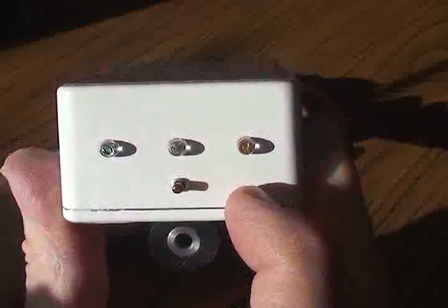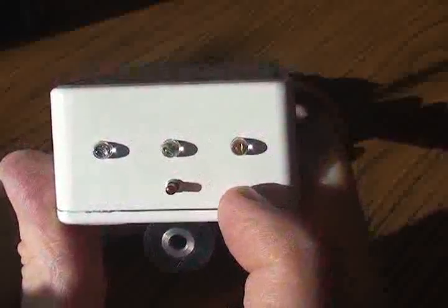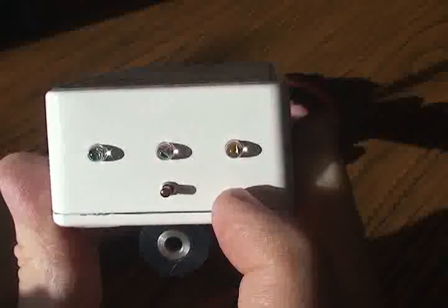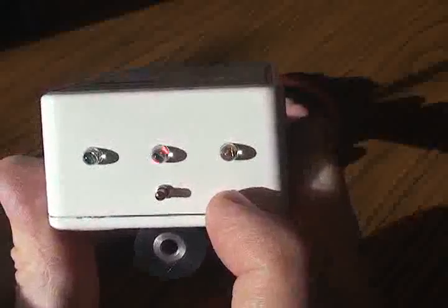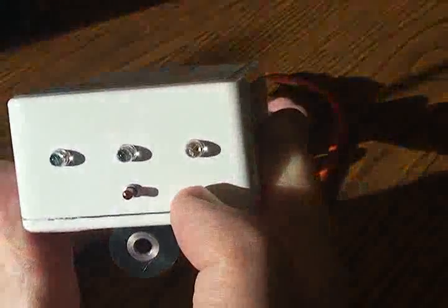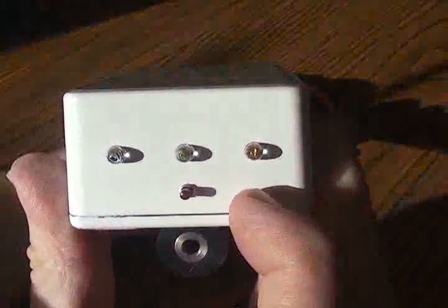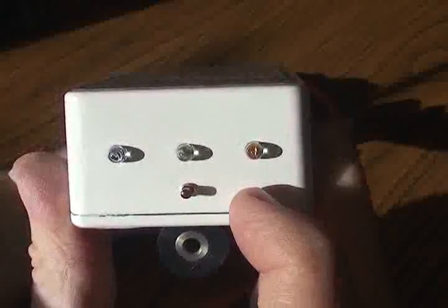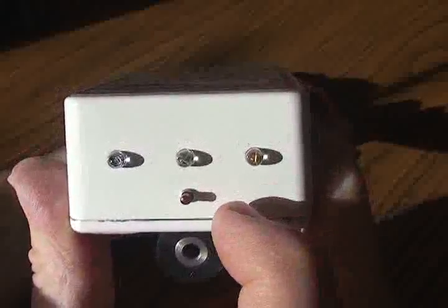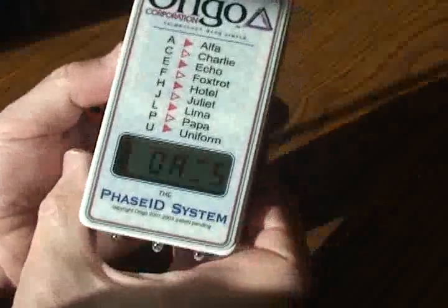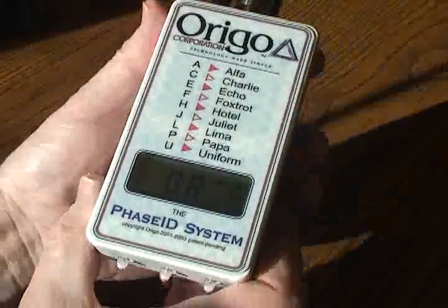So you want to wait now. And what I'm getting is a red light blinking, that means I'm on phase B. I can confirm that by looking at the field PC. So once you've seen that you have the correct data, go ahead and touch the red button again, and that'll turn it back off so you can go for your next reading.